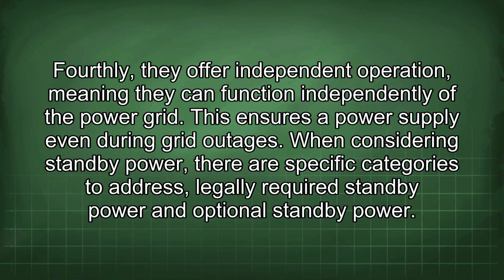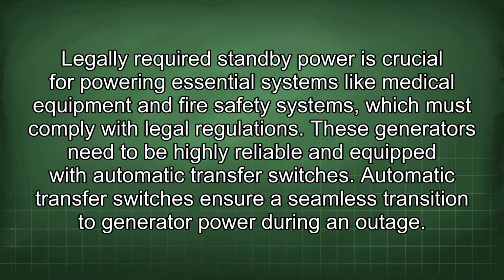When considering standby power, there are specific categories to address: legally required standby power and optional standby power. Legally required standby power is crucial for powering essential systems like medical equipment and fire safety systems, which must comply with legal regulations. These generators need to be highly reliable and equipped with automatic transfer switches. Automatic transfer switches ensure a seamless transition to generator power during an outage.